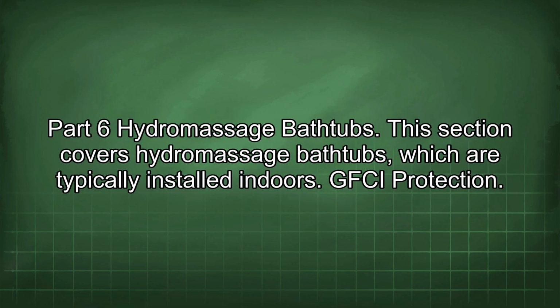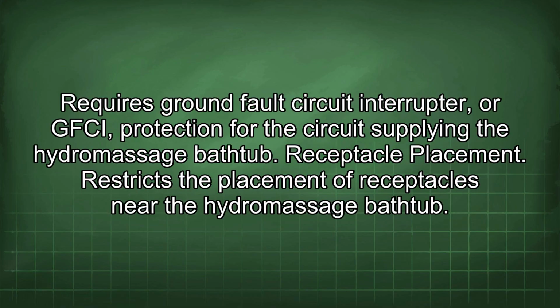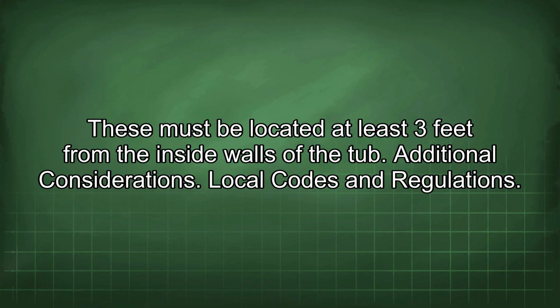Part 6. Hydromassage bathtubs. This section covers hydromassage bathtubs, which are typically installed indoors. GFCI protection. Requires ground fault circuit interrupter, or GFCI, protection for the circuit supplying the hydromassage bathtub. Receptacle placement. Restricts the placement of receptacles near the hydromassage bathtub. These must be located at least 3 feet from the inside walls of the tub.